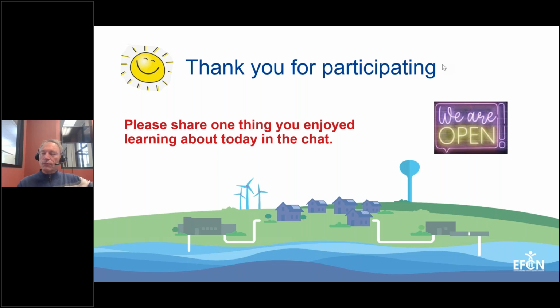Awesome. I got two more for you. Someone was wondering, the CT, is that dose times contact time, or the residual times contact time? It's the residual. When you calculate the CT value, you measure the free residual after the process. At the end of the contact basin, for example, you have a monitoring point. The dose isn't relevant, because you want the free residual that's still remaining after the process, since that's something you can depend on. You might put in a large dose and let's say every single bit of it gets used up by reducing compounds; it wouldn't be relevant. So you want to look at the free residual that's remaining. Good question.